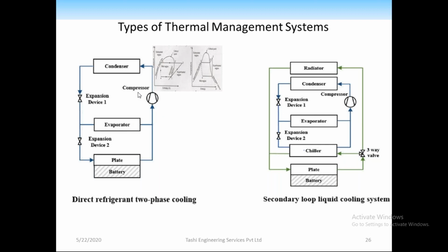In direct loop cooling, it's basically the same as an air conditioner used for cabin cooling. This is the cold plate—in direct cooling, I pass refrigerant directly into the cold plate. In secondary loop cooling, I use that refrigerant to cool a water-based ethylene glycol mixture, and pass that ethylene glycol-water mixture instead. The advantage of direct cooling is that it helps avoid most heat exchangers, making the system very simplified.